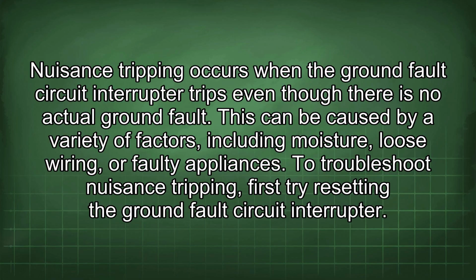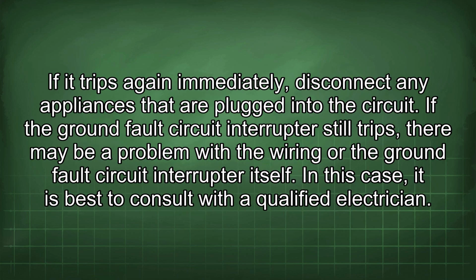To troubleshoot nuisance tripping, first try resetting the ground fault circuit interrupter. If it trips again immediately, disconnect any appliances that are plugged into the circuit. If the ground fault circuit interrupter still trips, there may be a problem with the wiring or the ground fault circuit interrupter itself. In this case, it is best to consult with a qualified electrician.